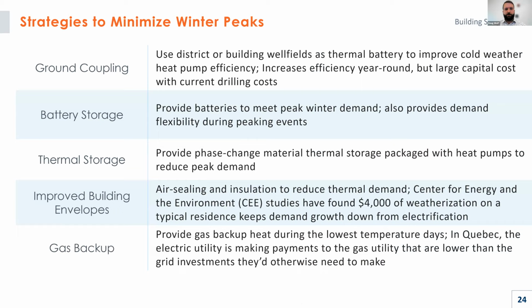There's battery storage, thermal storage, which might include things like phase change materials or ice storage. Improving building envelopes, as we just talked about, and utilizing gas backup. So instead of electric resistance or electric strip heating to back up your heat pumps, provide some natural gas at those times, because it's those peak morning hours during winter that are going to be very unwieldy for grid operators to manage and for utilities to provide enough power.